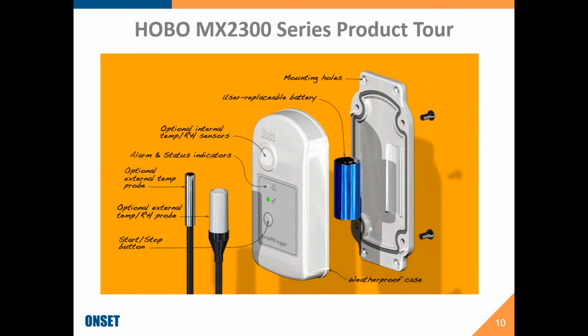Also over on the left of this diagram, you can see the artist renditions of the external temperature or the external temperature and RH probes. Just above the button are the status indicators. There's one that's just an operation indicator that tells you that it's logging. And then there's another indicator that's the indicator of an alarm, and I'll talk a little bit more about the alarms later on. Above that is the vent for the internal temperature and RH sensors. So if you have a version that has the internal temperature sensors, they're located in there.